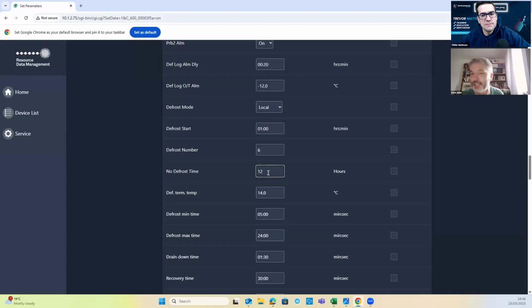So if you're sending it an external signal and it doesn't see that signal for that many hours, it's going to give you a missed defrost alarm, and it's going to go into an emergency defrost. If it's gas and it's initiated from the pack, you'll get an off-cycle defrost. If it's electric and it's just getting a remote signal, you will get a defrost at that time, and it's going to give you a missed defrost alarm, so you know it's done it.